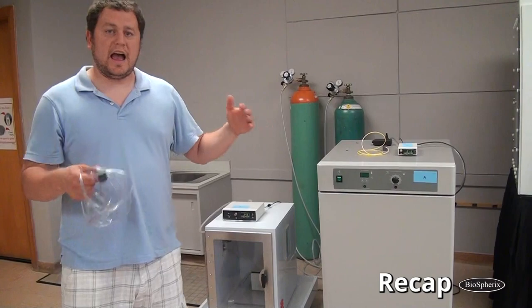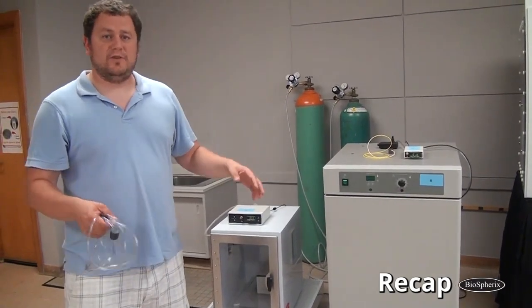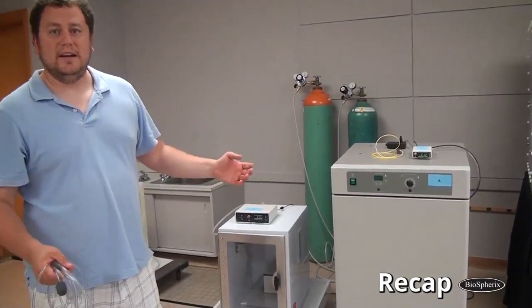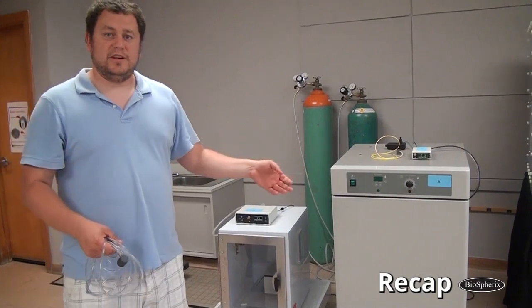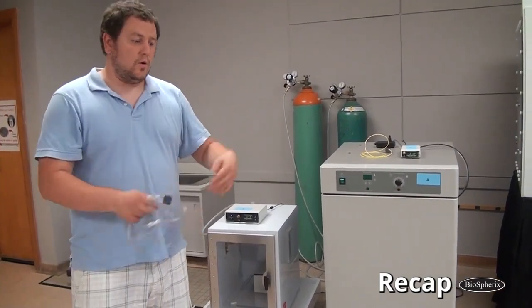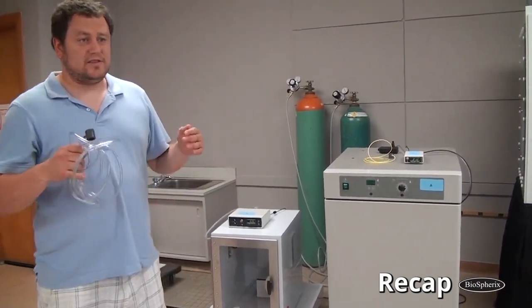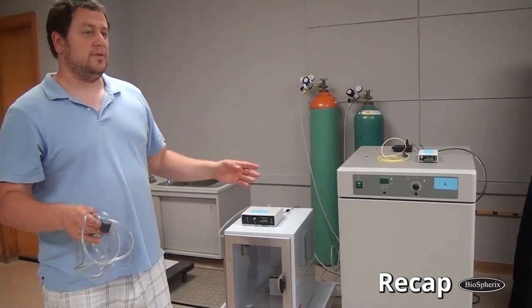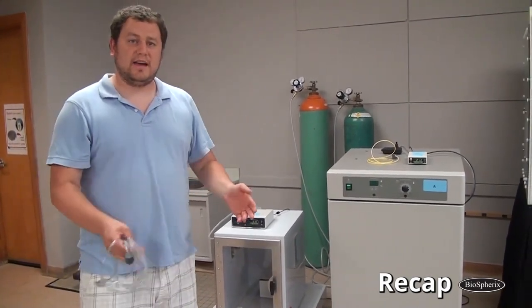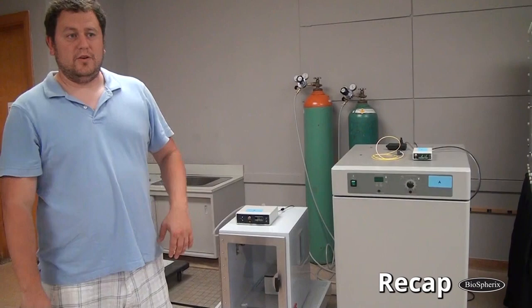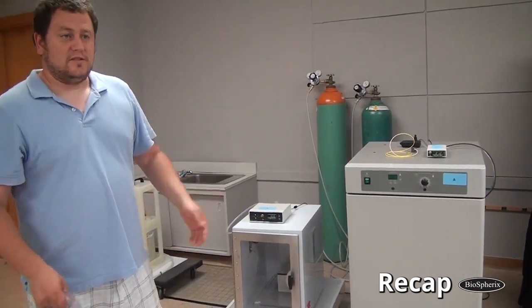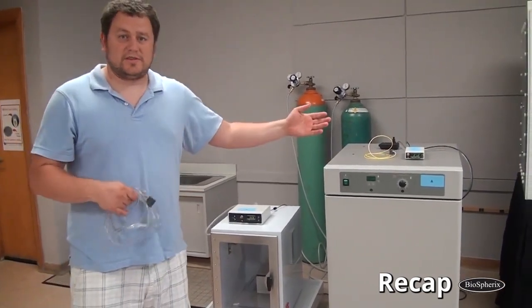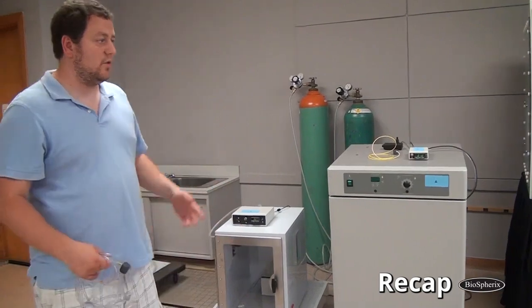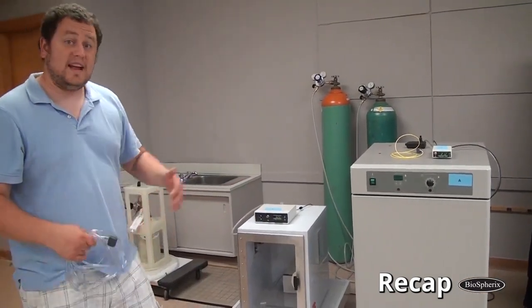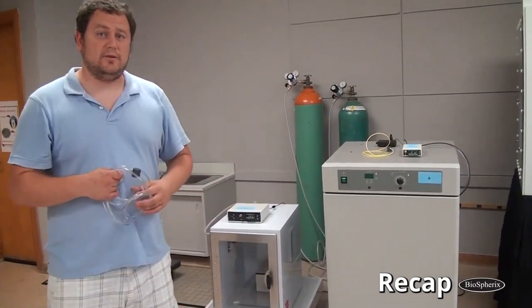If you see something odd, or that calibration coefficient seems really out of line from where it started on your green sheets, your setup sheets, or what you've been keeping track with, that's your big red flag. Hey, there's something wrong with my sensor. It's probably time to change it, or it's failed, or if it's a brand new sensor, give service a call here, and we're more than happy to talk you through. But that's how to calibrate your model E702.